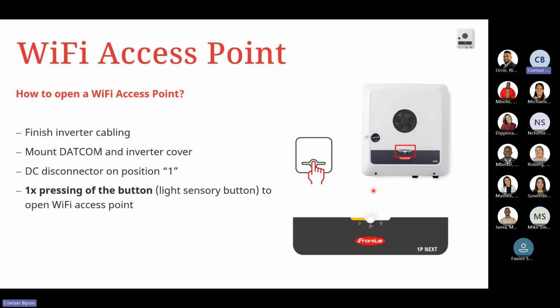Once you have done the AC DC connection coming into the unit, we can then do the commissioning of it. This will allow us to do the Wi-Fi access point. So how do you open the Wi-Fi access point? Once you've done the installation itself, we will hold our finger over the light sensor button in the middle of the unit, and this will allow us to open the Wi-Fi access point. Once the right hand side LED is flashing blue, that means the access point is open, and we can now connect to it either via a laptop or phone to start the commissioning process.